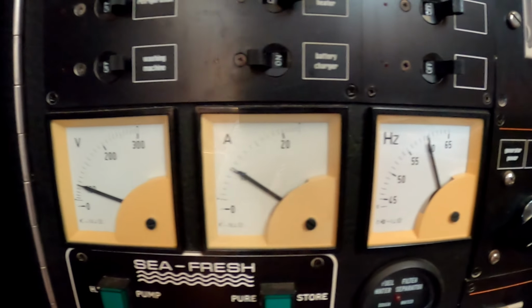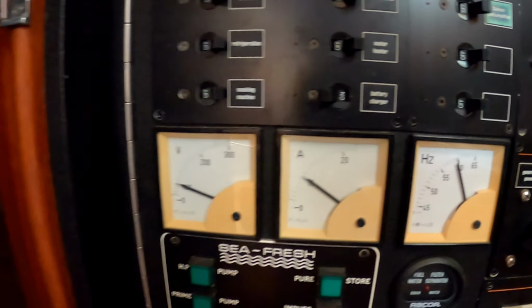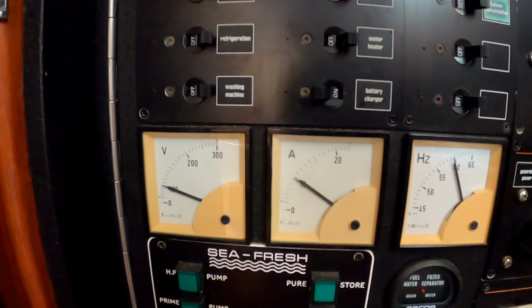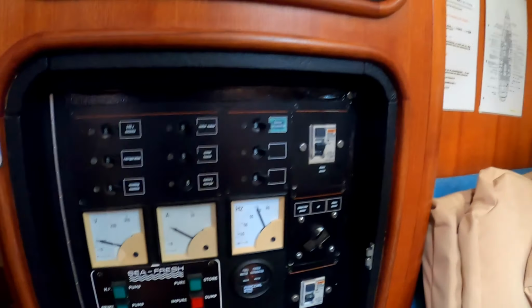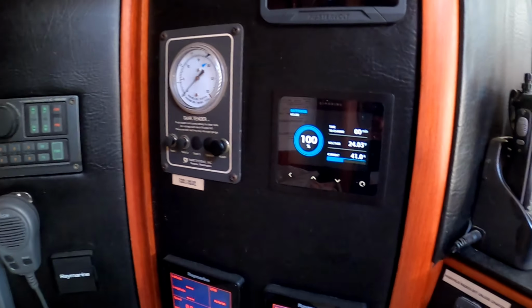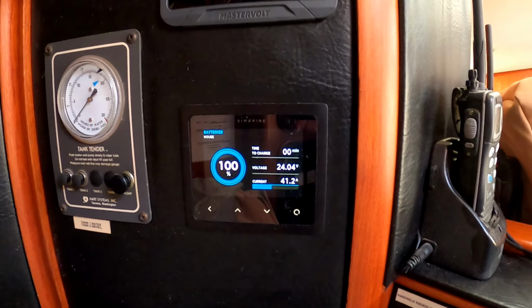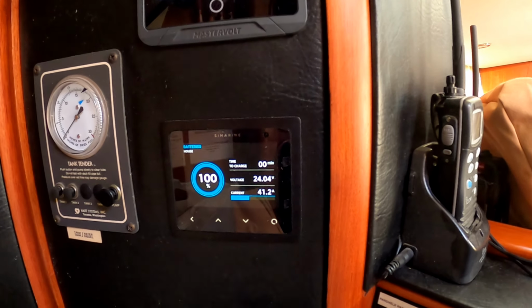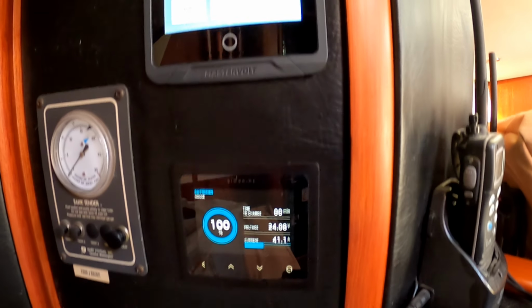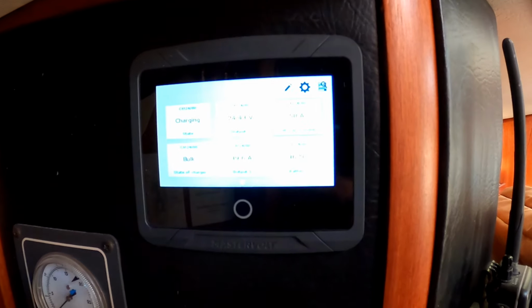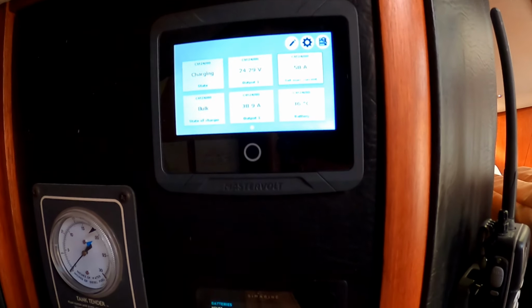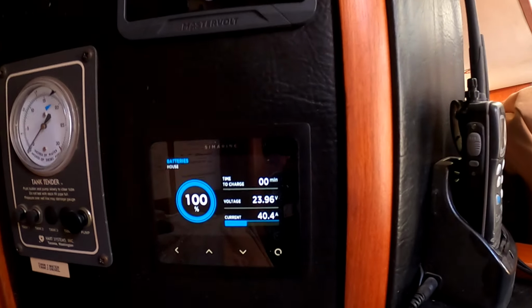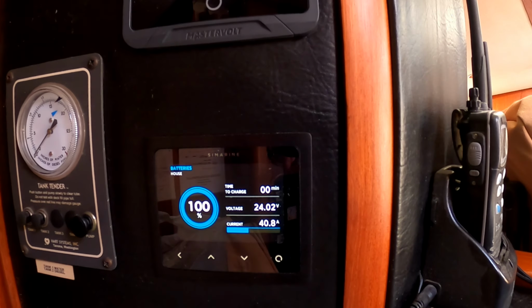At a little bit less than 60 hertz, right now the battery charger is drawing about 10 amps. It's not running at full capacity. It's throwing in 41 amps, and that's net. At the charger it's putting off 58 amps, so we're losing some amperage there. I think that's just what's going into the batteries.